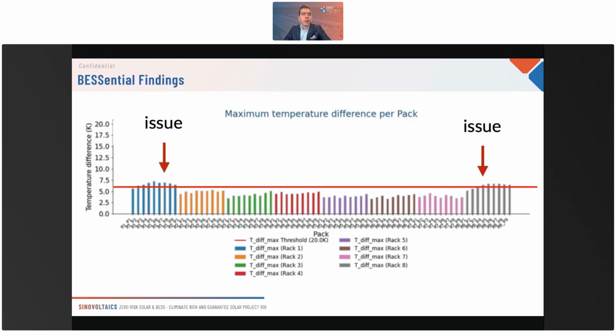Here's one example: these are temperature differences within the modules inside of the container. Each of these columns represents a module, and the color coding shows which rack it's from. You can see that for some of the modules the temperature differences were too high, so they were considered to be the issue here.